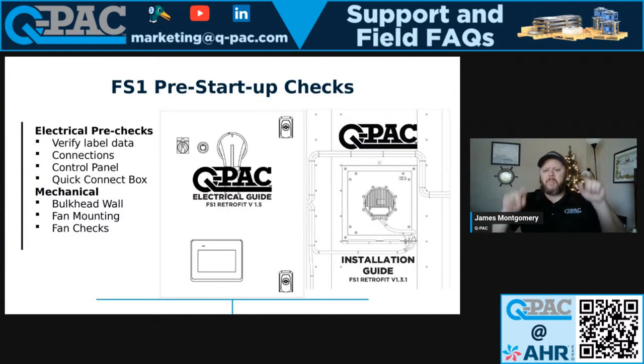Also, how is that bulkhead mounted within your structure? Whether this be a custom cabinet, an existing unit, maybe a custom built unit, or maybe a space that you're installing this in where your old fans lived. How is it secured? Is it secured well enough? You've got to think that depending upon the static and the amount of forces that we're going to be applying here with fans, a lot of times you see vane axial fans. The bigger ones are shock mounted and they've got these heavy duty concrete pedestals. If they're not concrete, they're steel and concrete to absorb all of the axial thrust that's going to come from that motor. Now we're spreading it across a big wall, sometimes a small wall. You need to be able to prepare for all those forces that are going to come through. And that happens at the installation phase. But prior to startup, you want to check these things because if you run this thing and it's not done correctly, that's catastrophic.